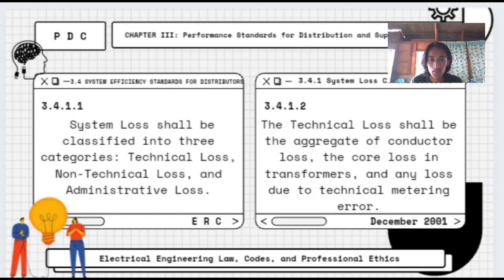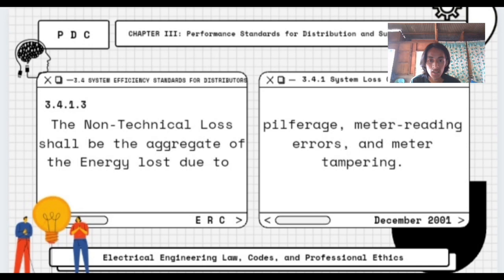Moving on to system efficiency standards for distributors, the first topic is system loss classifications. System loss shall be classified into three categories: technical loss, non-technical loss, and administrative loss. Technical loss shall be the aggregate of conductor loss, core loss in transformers, and any loss due to technical metering error. Non-technical loss shall be the aggregate of energy loss due to pilferage, meter reading errors, and meter tampering.